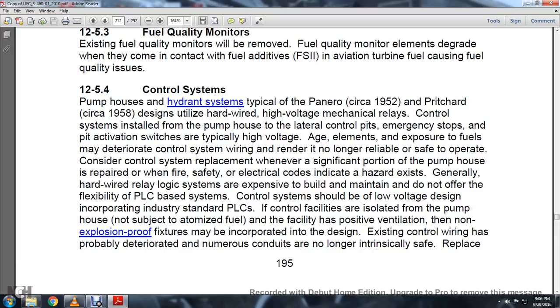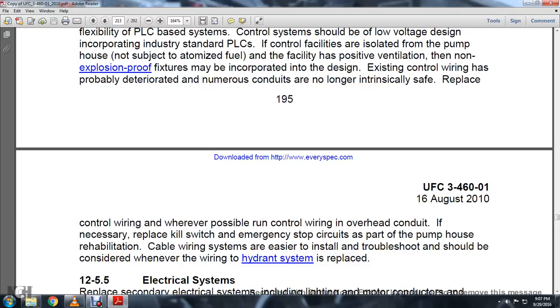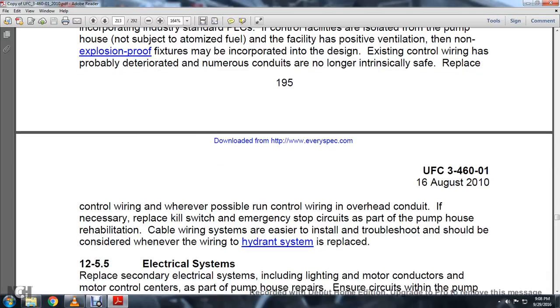Section 12-5-4: The pump house and hydrant system. Systems typically designed in the 1950s used hardwired high-voltage mechanical relay control systems installed in the pump house, lateral control pits, and emergency stop pit activation systems, with high-voltage elements exposed to fuels that deteriorate the control system, rendering it no longer reliable or safe to operate. Consider control system replacement whenever a significant portion of the pump house requires upgrade for safety or electrical code compliance. Generally, hardwired relay logic is expensive to build and maintain and does not offer the flexibility of PLC-based systems. The control system should be low-voltage, incorporating industrial-standard PLCs. If control facilities are isolated from the pump house (not subject to atomized fuel) and have positive ventilation, then non-explosion-proof fixtures may be incorporated into the design. Existing control wiring has likely deteriorated; replace control wiring where possible, running overhead. Replace kill switch and emergency stop circuits as part of the pump house rehabilitation. Cable wiring systems are easier to install and troubleshoot, and should be considered whenever wiring and the hydrant system are replaced.